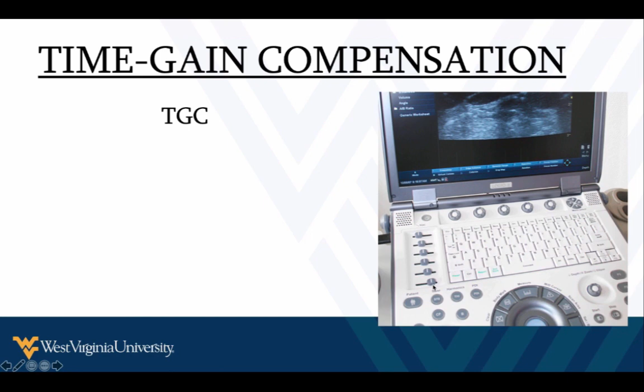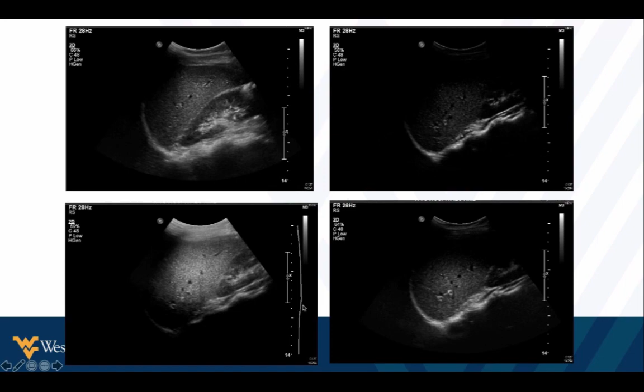So here are just some examples of how the time gain compensation may be changed or altered to affect your image. Here, this one looks pretty good. We see pretty consistent brightness all the way from the top of our image all the way down. This one, overall, I think probably it's too dark, and we've probably undercompensated here, so this whole band across our screen is dark. Kind of similar here, although the rest of this doesn't look too bad. Here we've turned our gain up too much at the top, but then we've lost it at the bottom. We have a band of darkness across our screen. This little line shows how we adjusted our TGC, and that would be suboptimal.